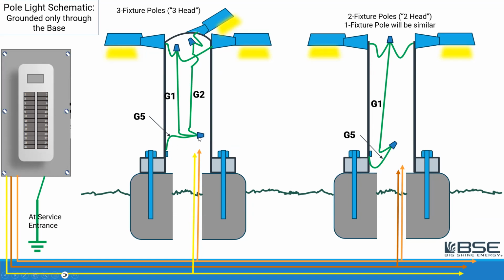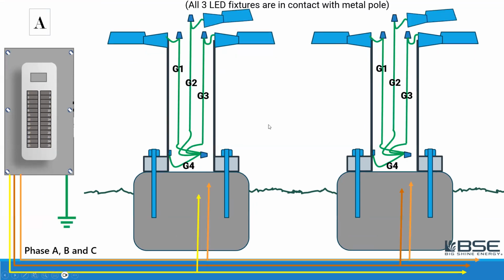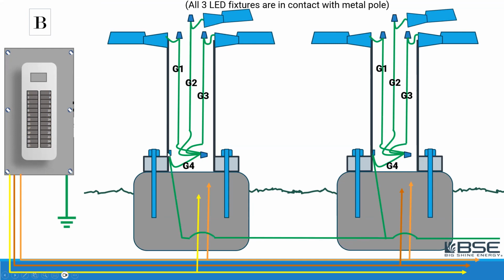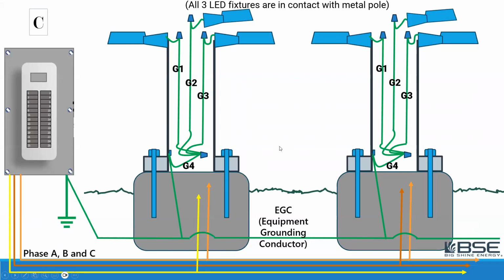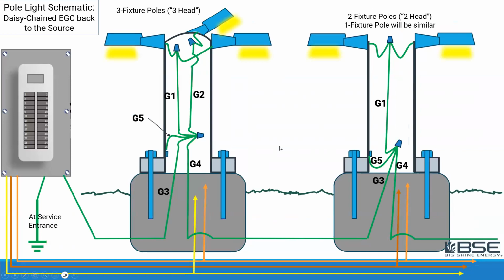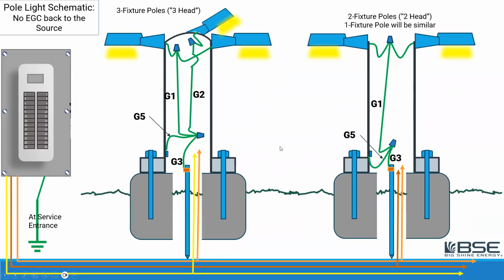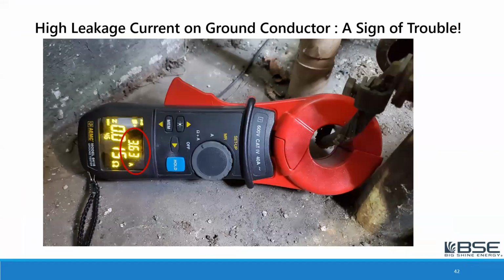This is also terrible for power quality. Then, you could have many of them connected together and then to a common connection to the pole. There might be a daisy-chained wire grounding conductor from pole to pole, but here you still don't see a path back to the source. So we've seen all of these different variations. And so it's very good, if you have concern, to get your maintenance team to just check this out and make their own schematic and show you what you actually have.